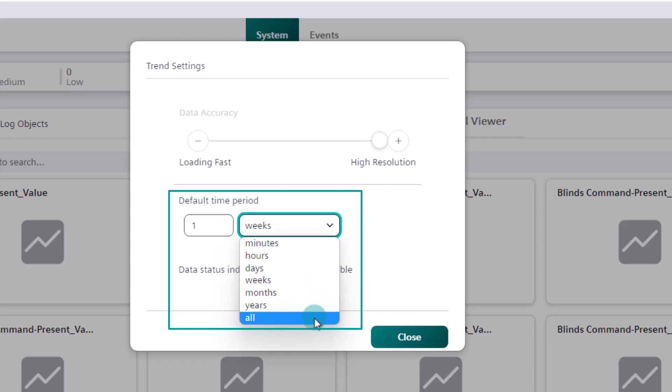CAUTION! The longer the period is selected, the longer it takes to load the data from the database. If all is selected, all data would be loaded for all trend object types. This can lead to very long waiting times, depending on the selected data accuracy and the amount of collected data samples in the trend database of Desigo CC.